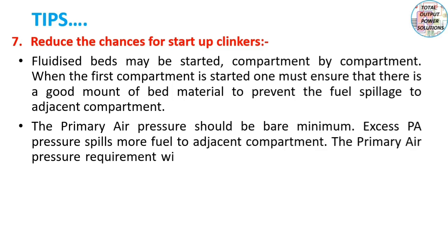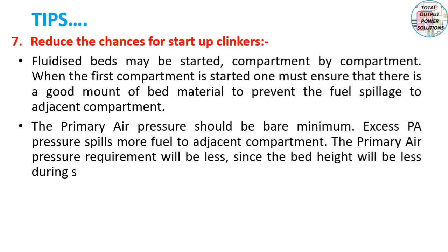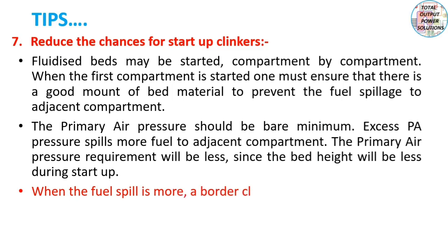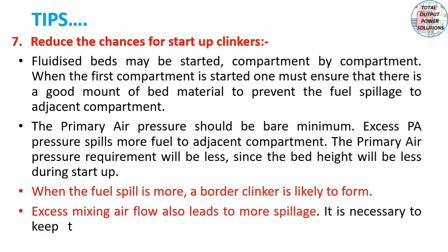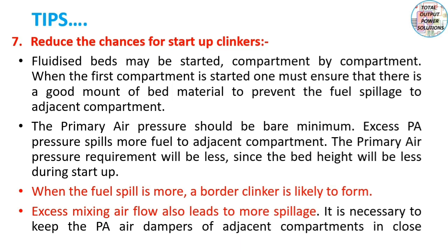The primary air pressure requirement will be less since the bed height will be less during startup. When the fuel spill is more, a border clinker is likely to form. Excess mixing airflow also leads to more spillage. It is necessary to keep the primary air dampers of adjacent compartments in closed condition.